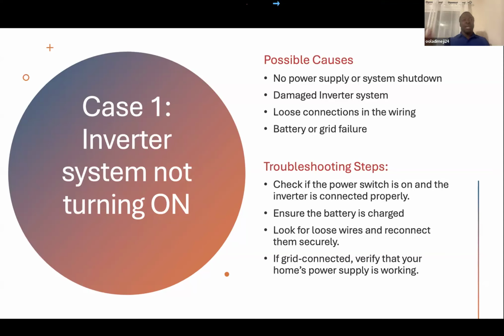If it's a battery connected inverter system, if the inverter is not getting the battery voltage needed to start up, it's not going to start up. So you want to be sure that the battery is charged, then check for loose wires and reconnect them securely. Sometimes terminals are not well tightened, like in an installation where one part of the battery terminal is not well tightened.